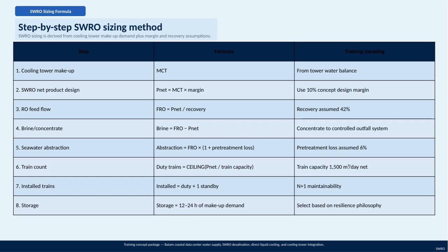Let's go through the step-by-step method for sizing an SWRO system, which is based on the cooling tower makeup demand, along with some margin and recovery assumptions. First, we start with the cooling tower makeup water demand, labeled MCT, which we obtain from the tower's water balance. This is the baseline amount of water required to compensate for losses in the cooling tower. Next, we calculate the SWRO net product design, PNET, by multiplying the cooling tower makeup demand by a design margin, in this case 10%. This margin accounts for uncertainties and ensures we have a reliable water supply.